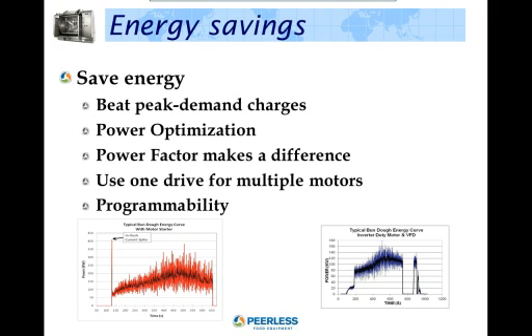Programmability. Users can program their VFDs to adjust the total acceleration time and current limit and adjust the speed to the load requirement. Current limit on drives is normally set between 105 and 110%, whereas the across-the-line starting method produces current limits of approximately 650%.